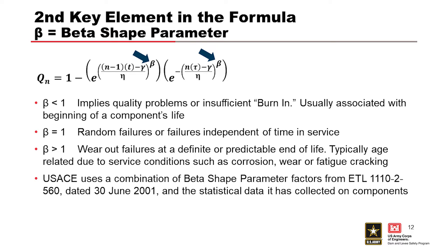A second key parameter element of the formula is the beta or shape parameter. It's really the slope of that curve at any point in time. A beta of less than one implies quality problems or insufficient burn-in, sometimes called infant mortality. A beta of one is more of a random-type failure.